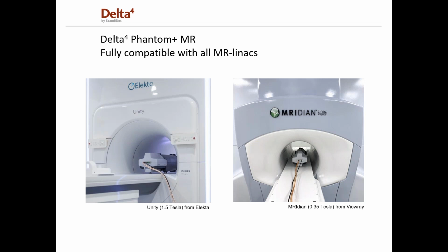There are several similarities between the MR Phantom and the standard Phantom Plus, and a few differences. We are compatible with both the Unity system and the MRIdian system, but as you can see, we have cables on this particular Phantom. This is the MR version. The reason being, of course, that Wi-Fi doesn't work very well in an MR environment. So we have two data cables and a power cable that connect to the Phantom and go to the power supply. We've had to remove all the ferrous items from the Phantom, and also we've remoted the power supply for the system.